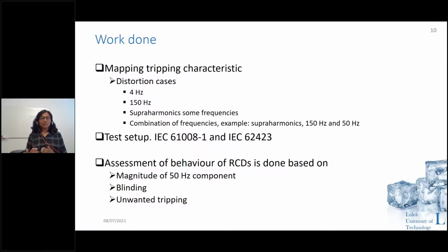We decided that we first map the characteristics of different RCDs. We have around 13 RCDs, and then we decided on separate distortion cases. We tested 4 hertz for quasi-DC. For harmonics, we tested with several, but I think the third harmonic is the most effective one, so I'll be presenting some results on the third harmonic as well. Then we did a test with supraharmonics at some frequencies, and also some combinations of supraharmonics, harmonics, and a fundamental component. These were the distortion cases that we used to test.